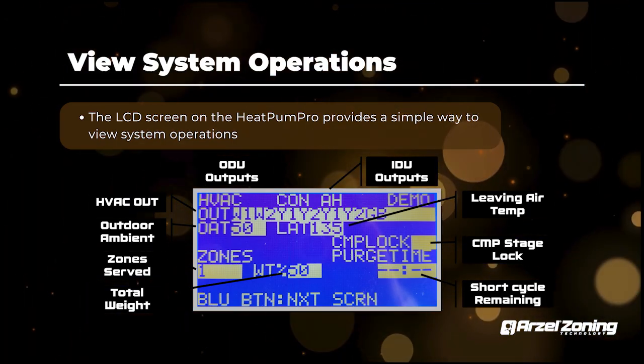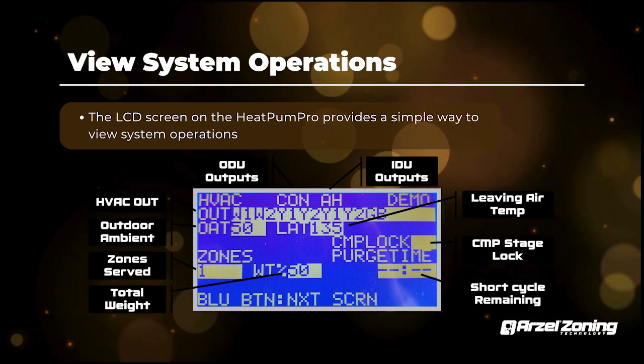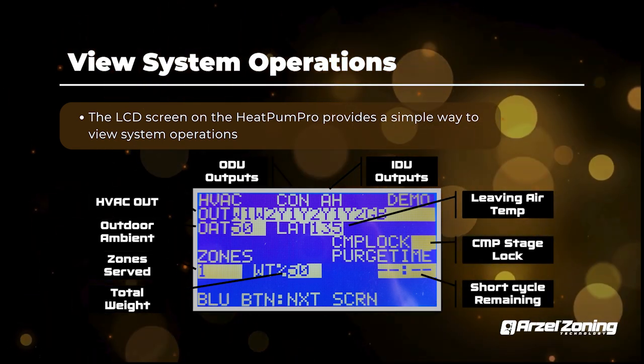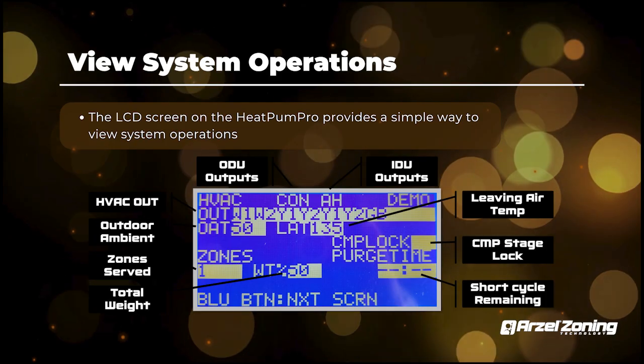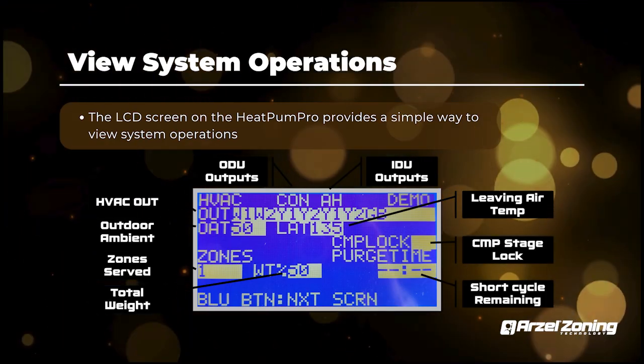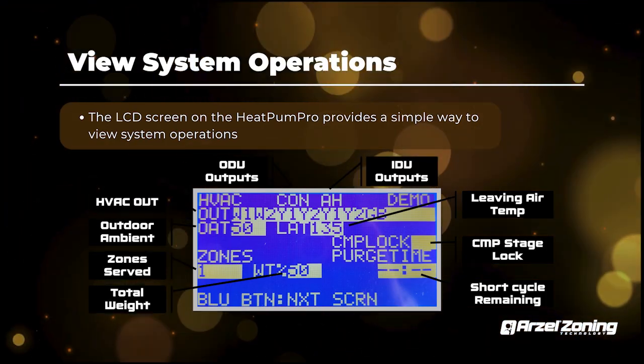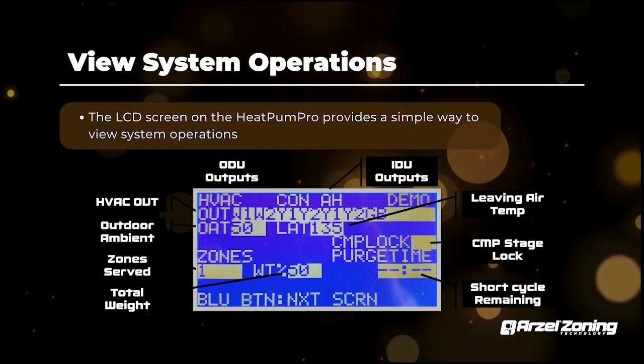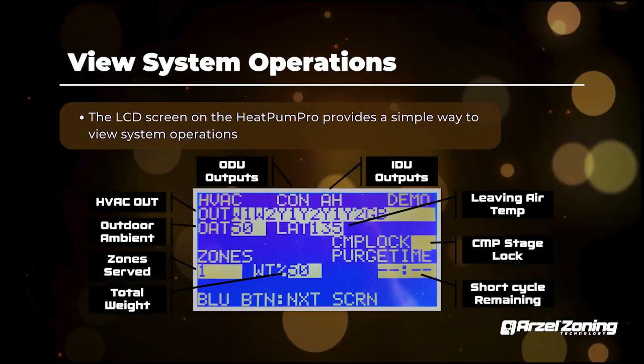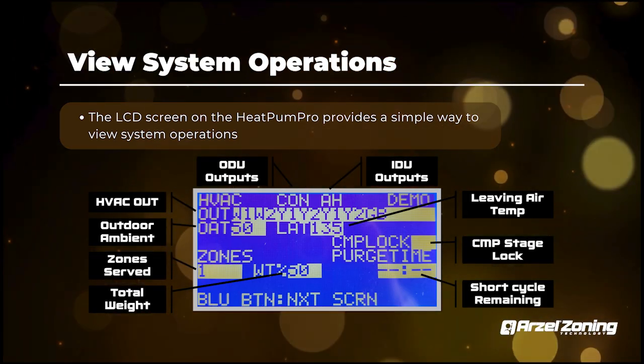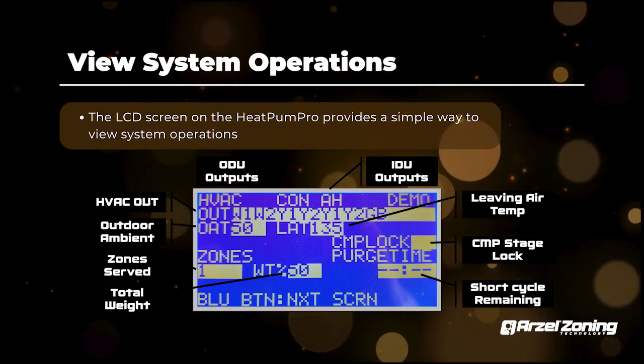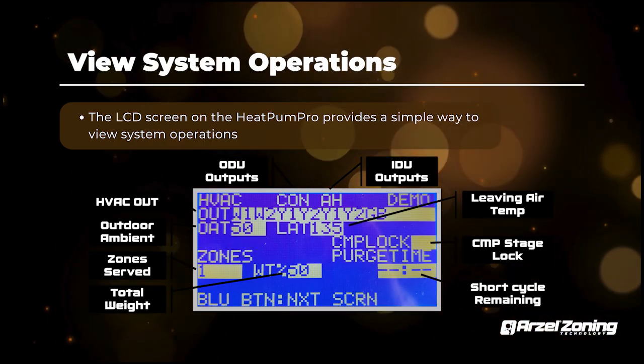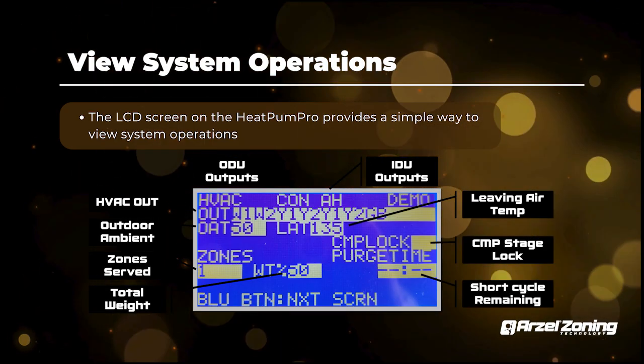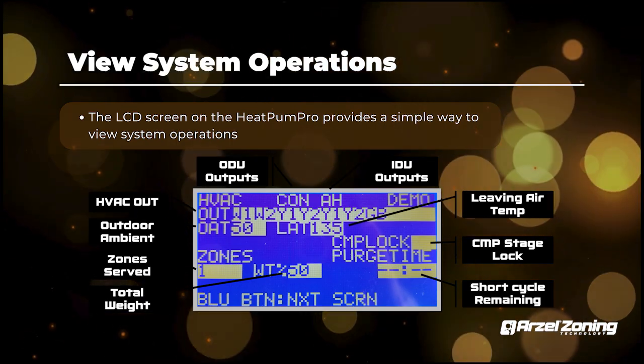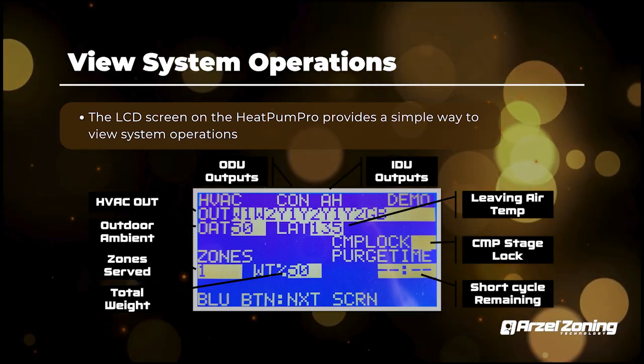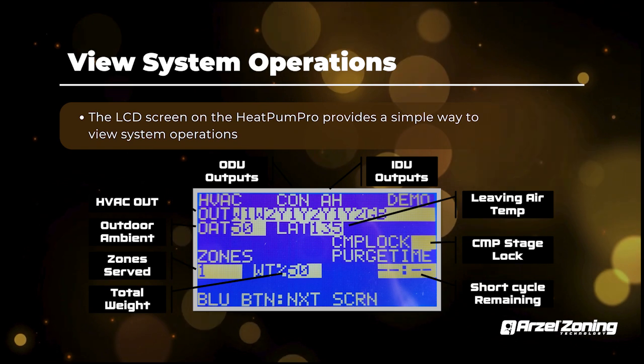And essentially when you're looking at this main screen, you're going to have HVAC on the top. Really doesn't mean anything, just there every time you see it. Then you're going to have CON-AH on the top. Right under CON is your Y1, Y2. That's your condenser, Y1, Y2. That would be if we were energizing Y1 or Y2 on the condenser. You'll see that underneath there. That'll tell you what we're actually outputting to your equipment. And then underneath air handler, you'll have Y1, Y2 as well. Those are your blower motor Y1, Y2 signals. So that's what we're sending to the air handler blower.